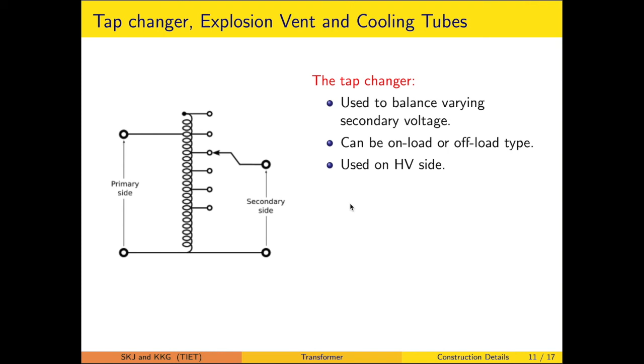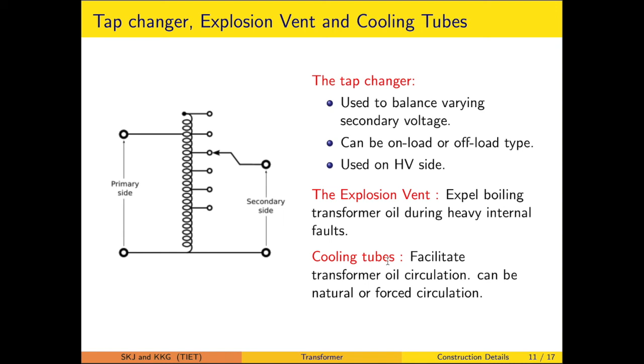Explosion vents are to expel boiling transformer oil during a heavy internal fault. So it is a mechanical arrangement. The cooling tubes are also provided to facilitate the oil circulation, and this has a cooling objective. It can be a natural cooled or force cooled circulation. In the force cooled arrangement, a fan and motor arrangement is worked out likewise.